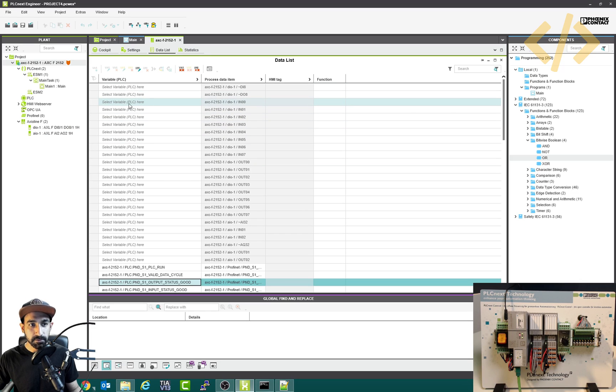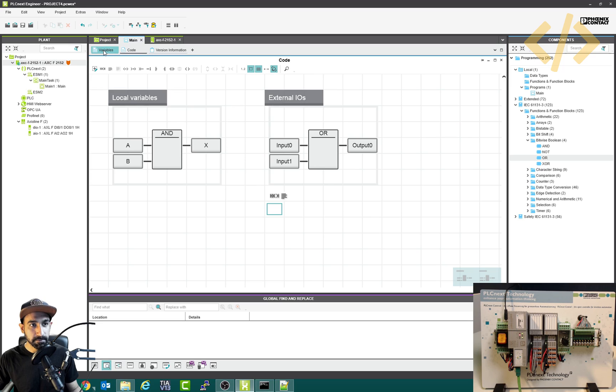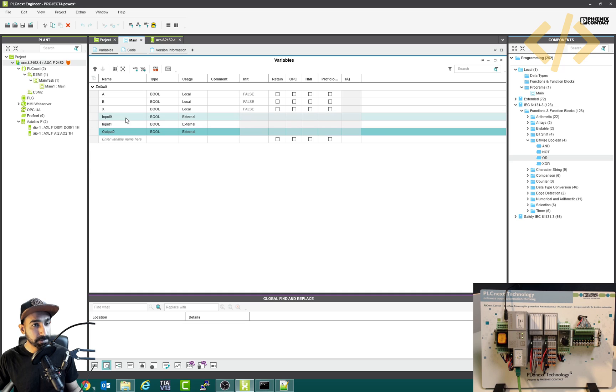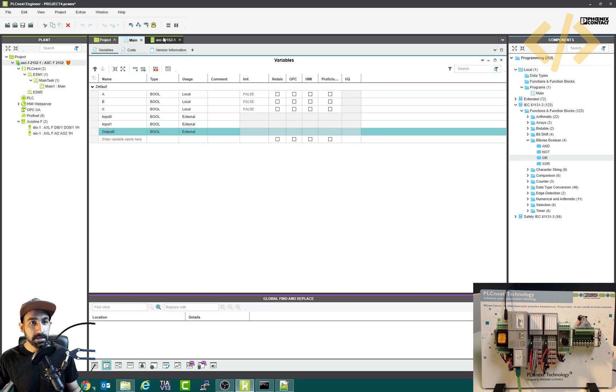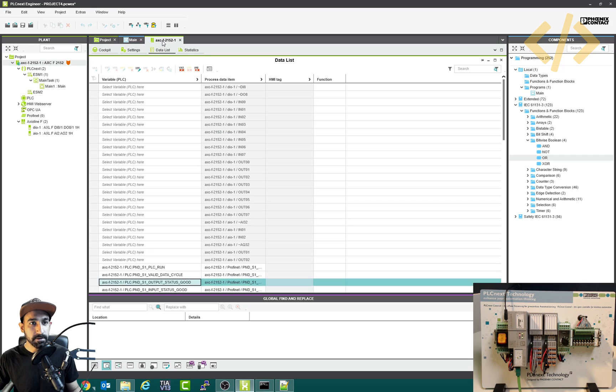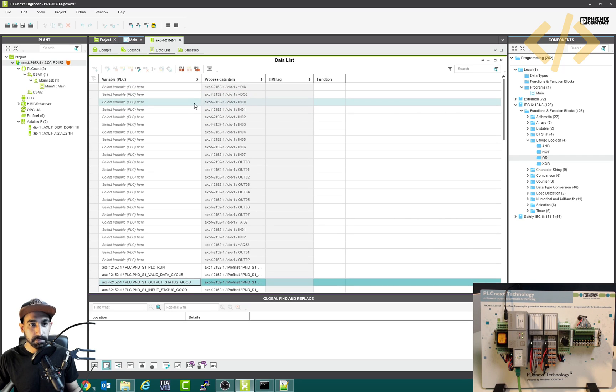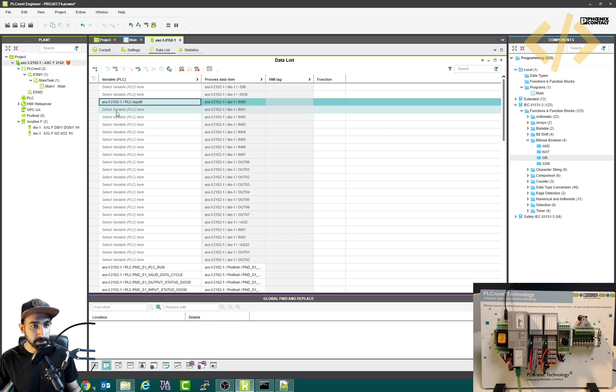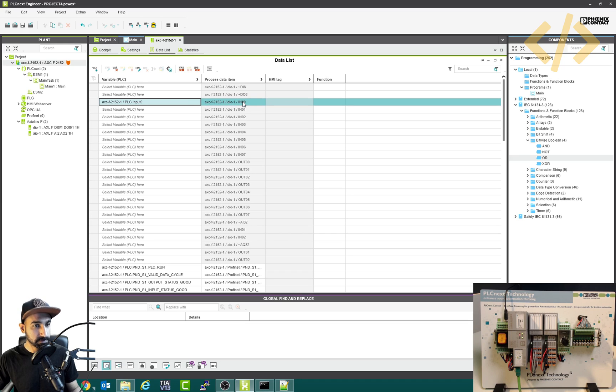So now we have to link the PLC variable which we defined in the main, in the variables like this. Input zero, input one, output zero, these are still variables in the PLC program. It's not linked to IOs yet. To do that, go back to here. And our input zero was in zero. So select this one and you can see three variables which were in the PLC. So I will select input zero. Now this is linked to my external input zero, this variable PLC input zero.